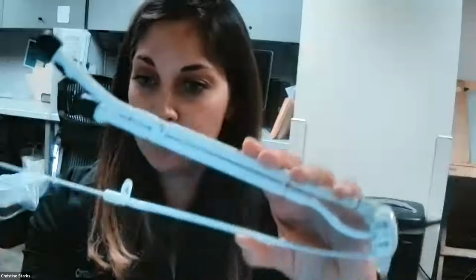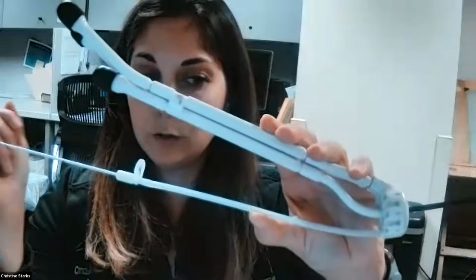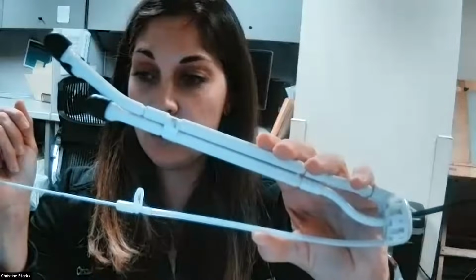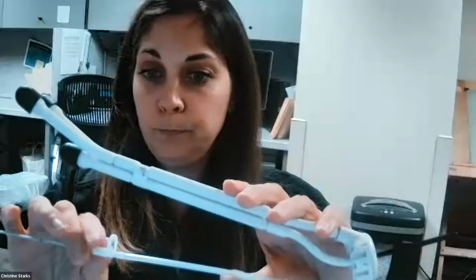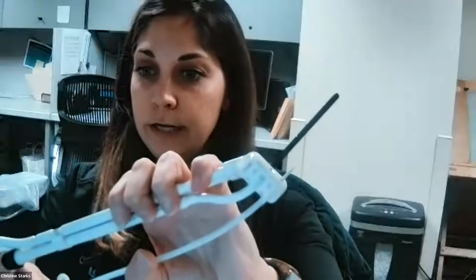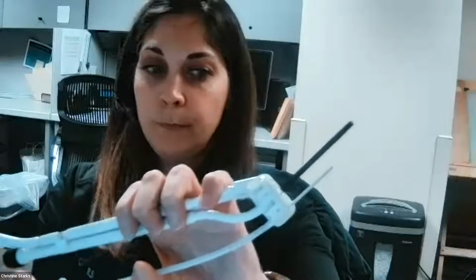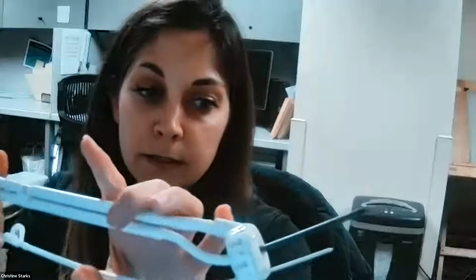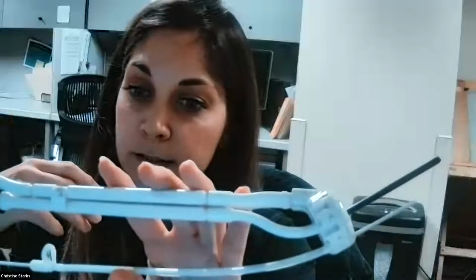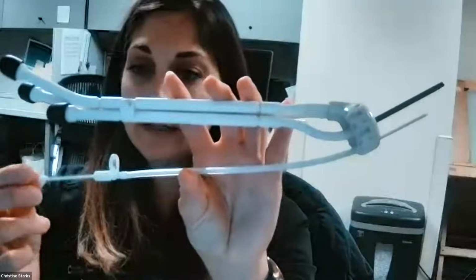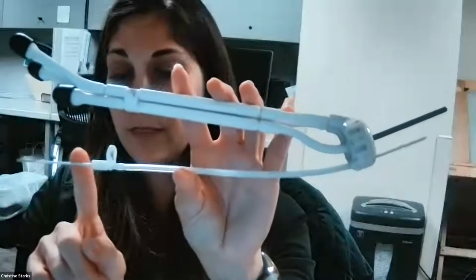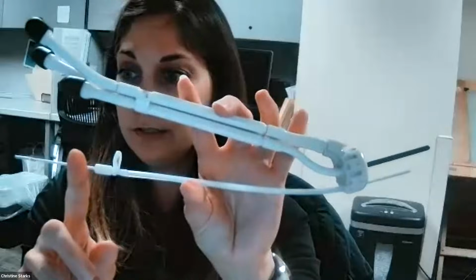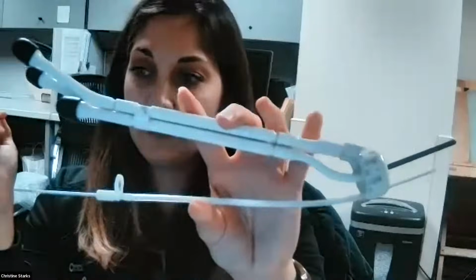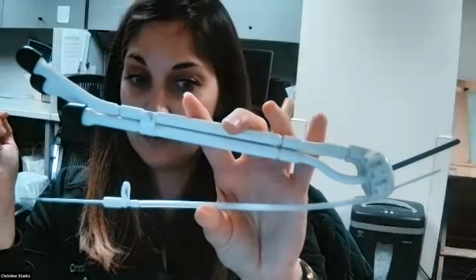Like Dr. Lin mentioned earlier, we can do needle guidance with ultrasound, CT, or MRI. Once you've unlocked the screw cap, you can advance your needle. When you're advancing the needle, we found that the longest needle length should not exceed 6 cm. That is because we need a 3 cm distance for the connector, for the 6 French connector tubes. So we found that 6 cm is the limit as far as advancing the needle into the cervix.